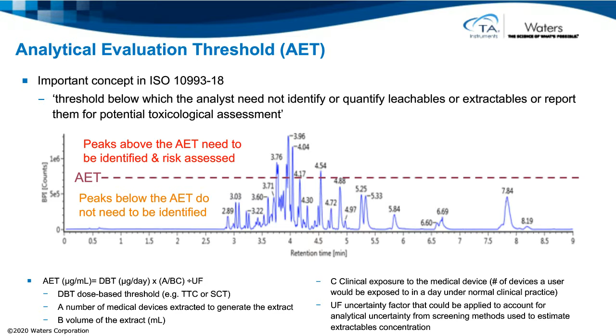So to this end, the term known as the analytical evaluation threshold is used. Now this is a very important concept within ISO 10993 Part 18. Below the calculated threshold, any extractables or leachables need not be identified nor quantified. This means, of course, that anything above this threshold, you need to identify the substance, you need to quantify the substance. You need to work with the toxicologist to understand what levels of compound are important.